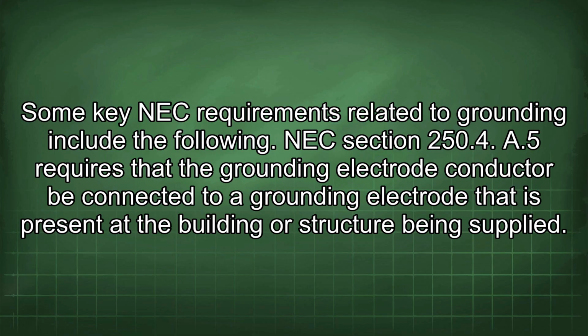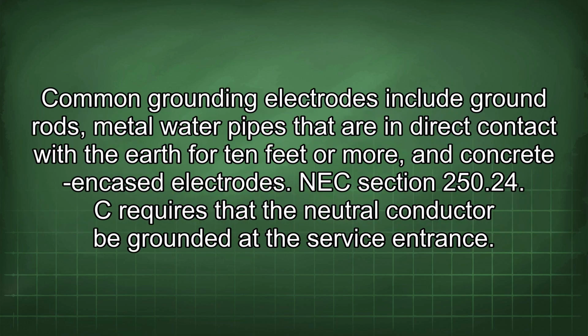NEC Section 250.4(A)(5) requires that the grounding electrode conductor be connected to a grounding electrode that is present at the building or structure being supplied. Common grounding electrodes include ground rods, metal water pipes that are in direct contact with the earth for 10 feet or more, and concrete-encased electrodes.